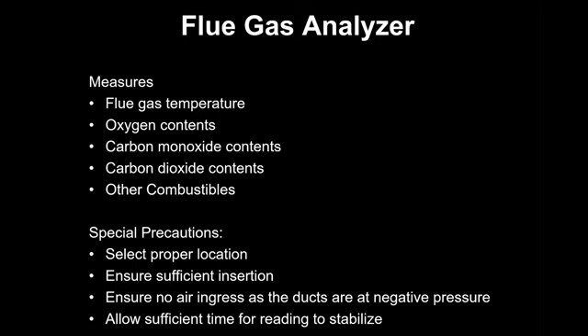The BEE formulas will tell you the same thing, based on some assumed composition of coal or other fuel, depending on the selection of fuel. But if the carbon is different in our case, then the readings are going to be different. So carbon dioxide is not actually measured, but oxygen, carbon monoxide, and flue gas temperature are measured, and based on that we can calculate through the BEE procedure the combustion efficiency. And other combustibles can be added. Now, if somebody really wants to measure carbon dioxide, then you can go for a basic instrument, that is ORSAT, which is still available, and do that measurement. But nobody does it for an audit.